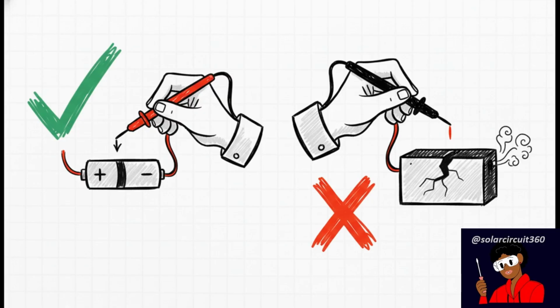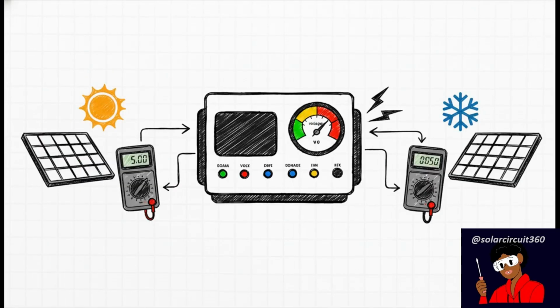Game over. Next up, checking the solar array's open circuit voltage, or VOC. Before you even think about connecting those panels to your charge controller, you need to measure the voltage coming off that string. Why is this so critical? Here's the thing about solar panels: their voltage goes up when it gets colder. So if you measure the VOC on a nice warm day and it's already close to your charge controller's max limit, what do you think happens on a freezing cold winter morning? You guessed it, you'll fry the controller. This one simple check prevents a very expensive mistake.